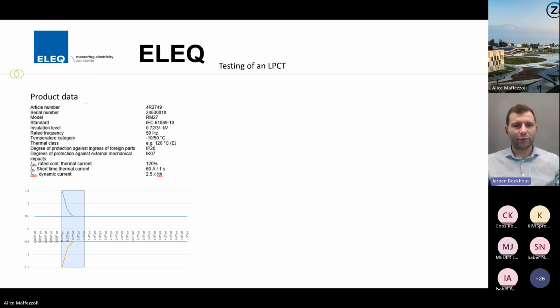So if we look into the product, here you can see the product data that we agreed upon. And below you can see in blue what the norm usually requires for a product of this type. In this case, I put in the borders of the class 0.5 product, which means you have 0.5% ratio error on the nominal current. In this case, it's a 5 amp to 1 volt CT. So that means on a primary of 5 amps, you expect less than 0.5% error.